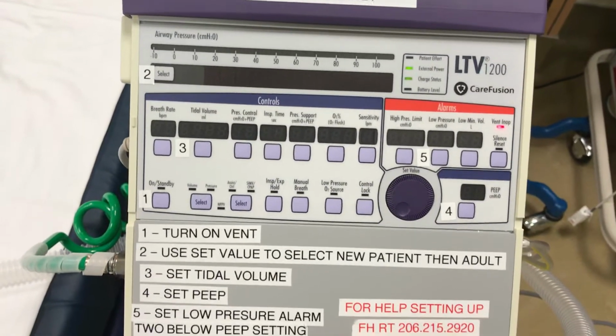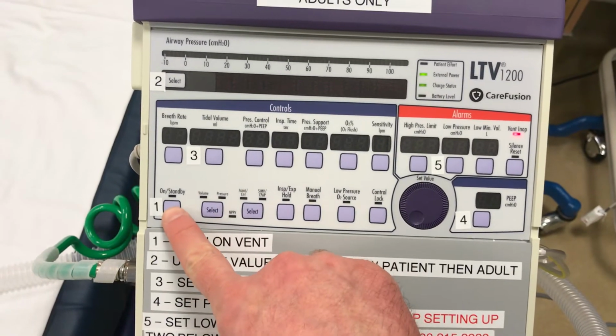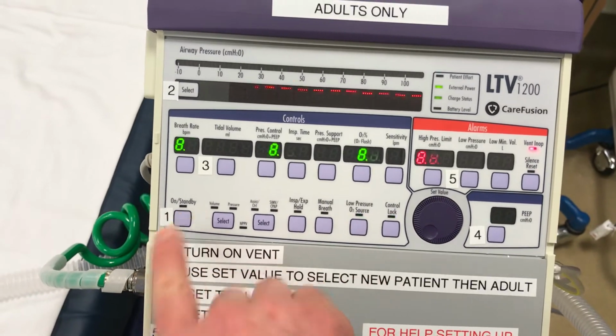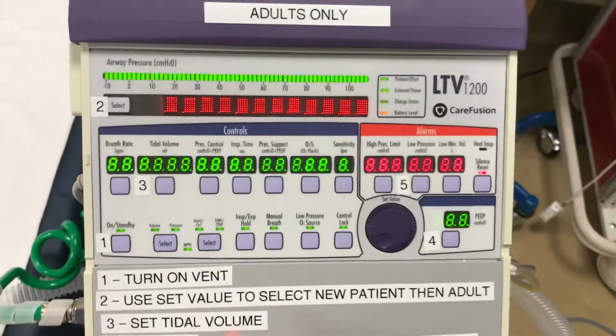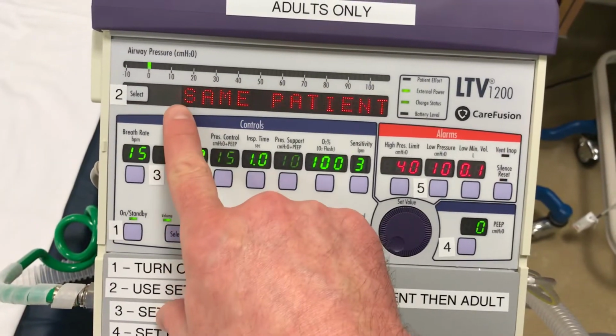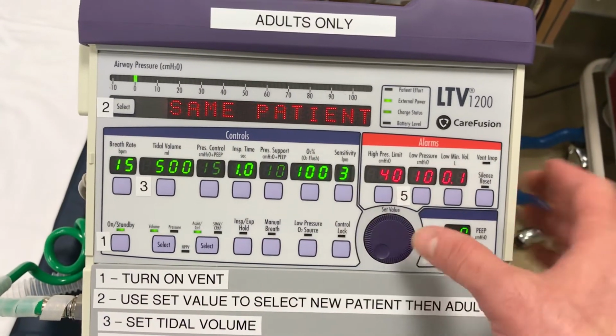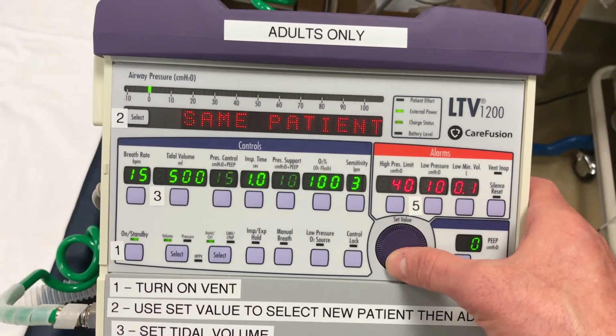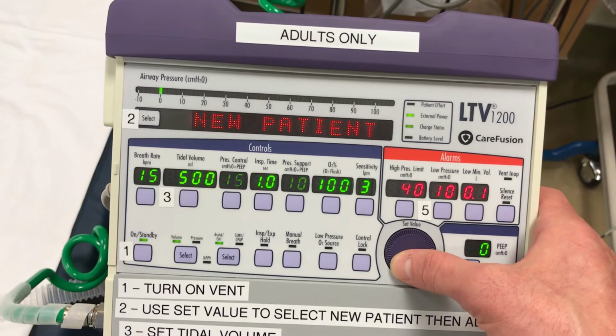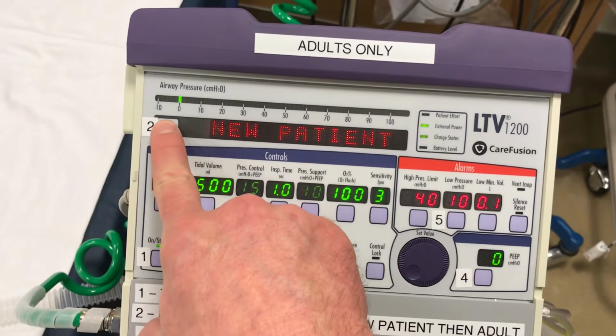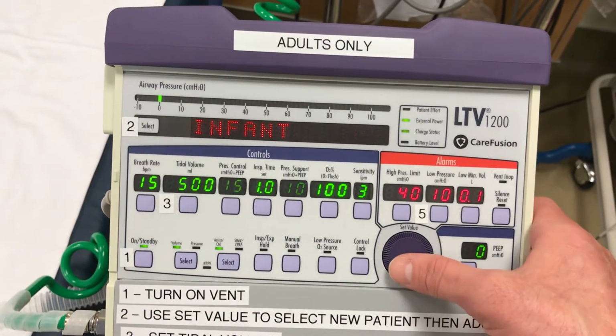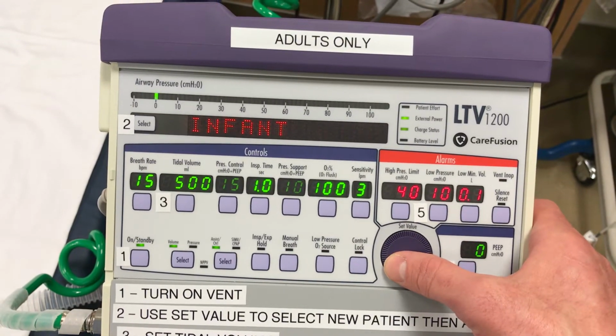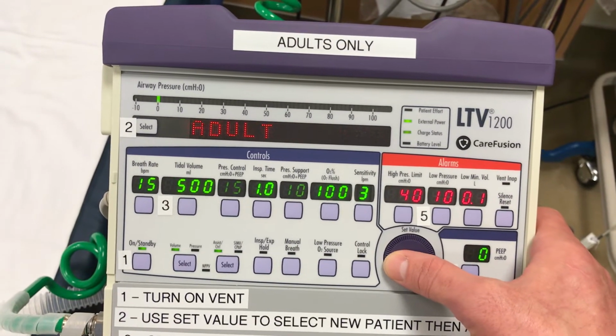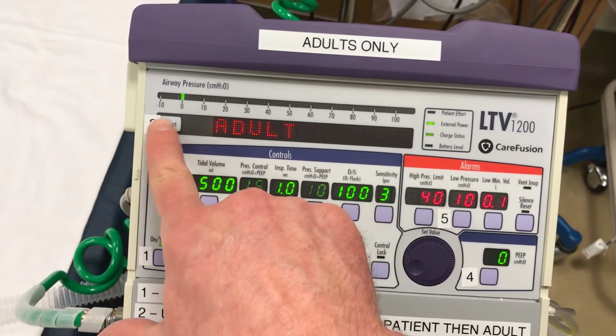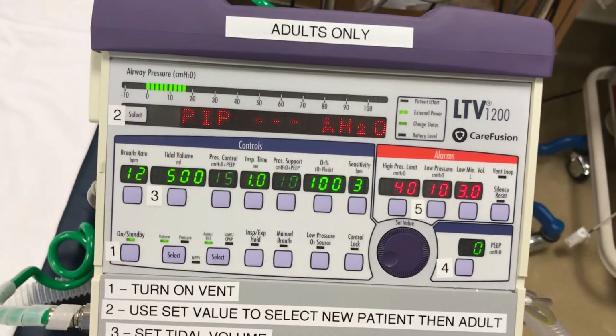Next, to turn the ventilator on, hit your on standby button. First thing you'll have to do is select whether you want same patient or indicate you want a new patient by rotating the set value dial to new patient and hit select. You'll have to indicate if you want infant, pediatric, or adult, and then choose by hitting select once again.